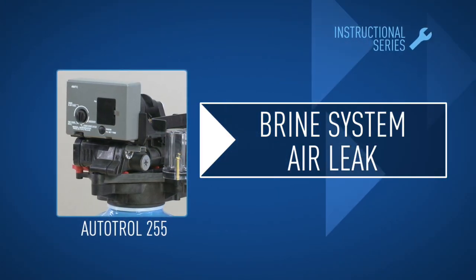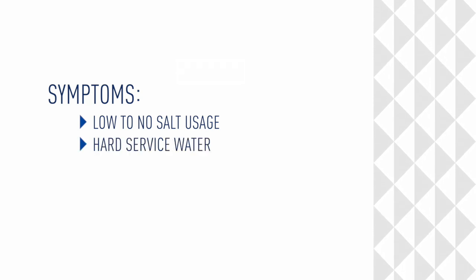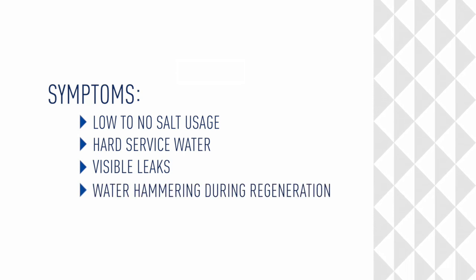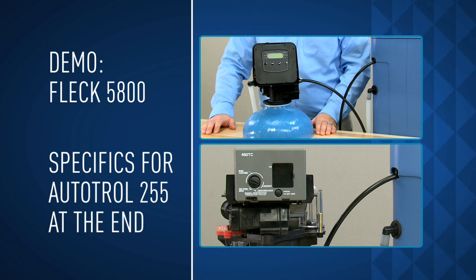In this module, we'll check for air entering a brine system and how to tighten or replace a damaged fitting or hose. Symptoms of air in a brine system include low to no salt usage, hard service water, visible leaks, or water hammering during a regeneration. We're using the FLECK 5800 as an example. At the end of this module, we'll identify the individual components of the valve you selected.